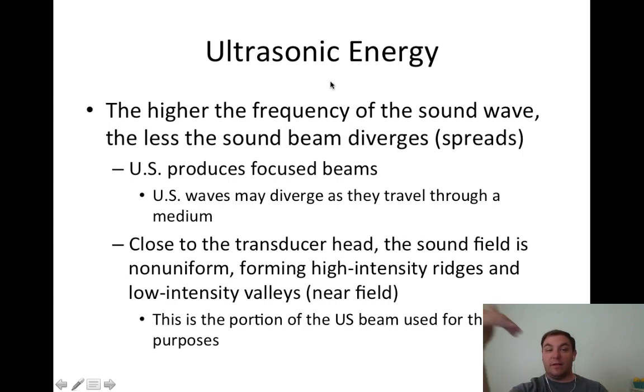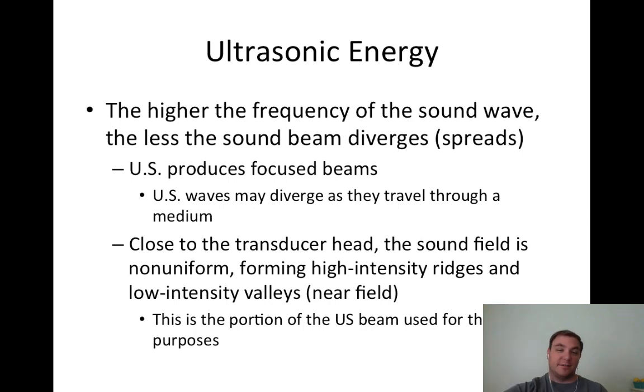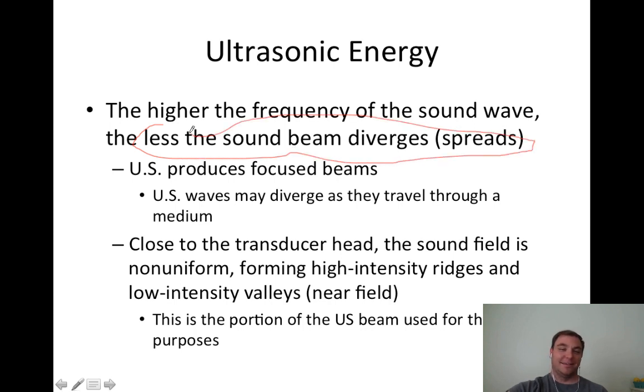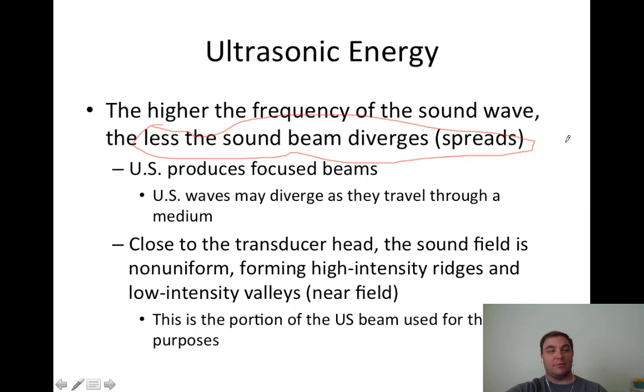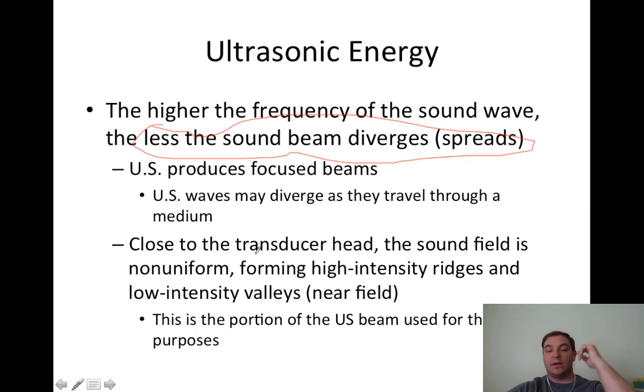The higher the frequency of the wave, the less the sound diverges or spreads. Ultrasound produces very focused beams, and the waves may diverge a little as they travel through a medium. Closer to the sound head, the sound field is non-uniform, forming high-intensity ridges and low-intensity valleys called near fields. This is the portion of the ultrasound beam used for therapeutic purposes.